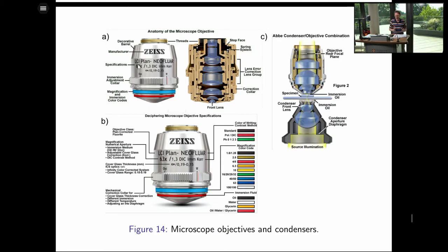So Zeiss has, I don't know what the standard tube focal length is. I think it's 200 millimeters, but it may range for different manufacturers from 160 to 220 millimeters. So they all have slightly different lenses. Because they're infinity corrected, you have to use the right tube lens to get the correct magnification and also the best possible imaging performance. So 1.3 is the numerical aperture. DIC is for differential interference contrast imaging, so this lens is optimized for a particular mode.